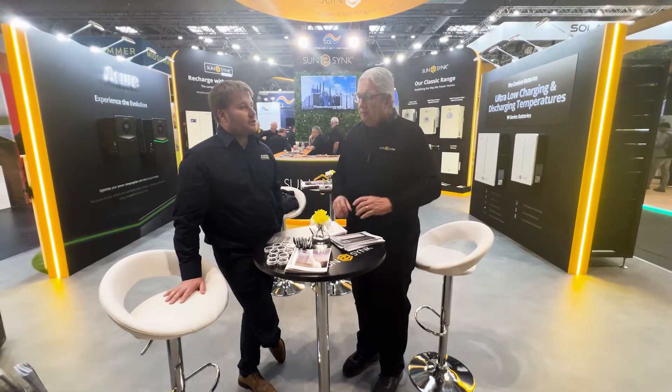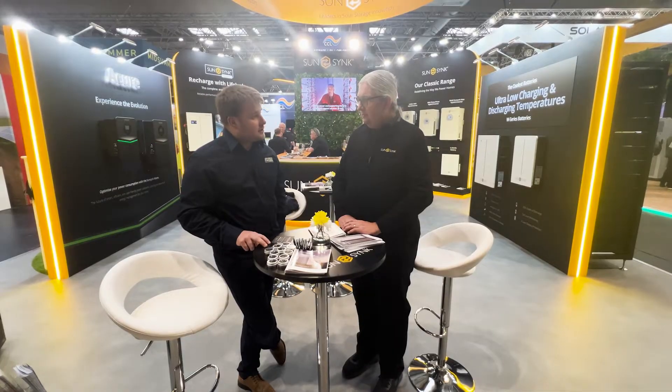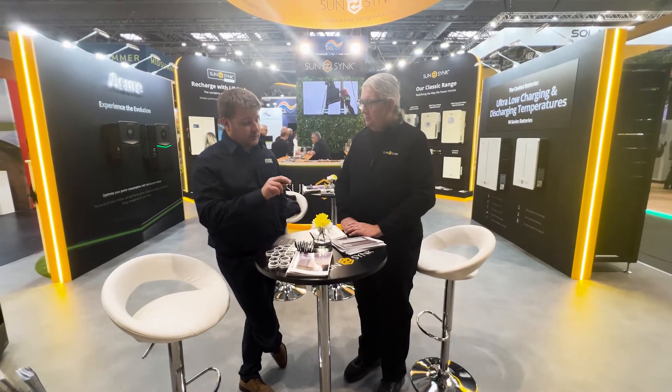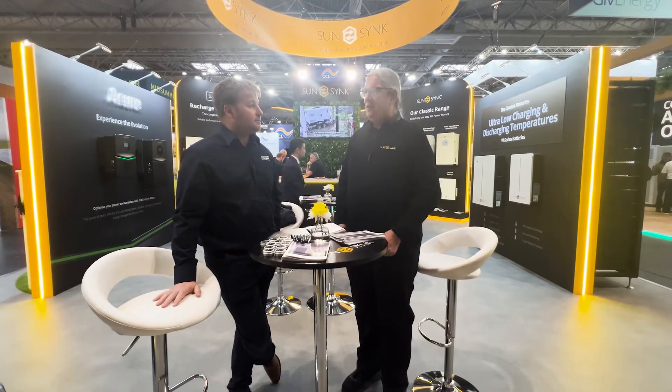I think it's also important for the South African market. What a lot of the guys are doing is they will use either relays or contactors, putting it on so that normally when Eskom fails and there's no voltage going to the coil, it's closing and then creating that bond. So there's no delay — it's all a split second. Yeah, very, very fast. That's not always so clever, and it can cause false nuisance tripping, so that's always a problem.